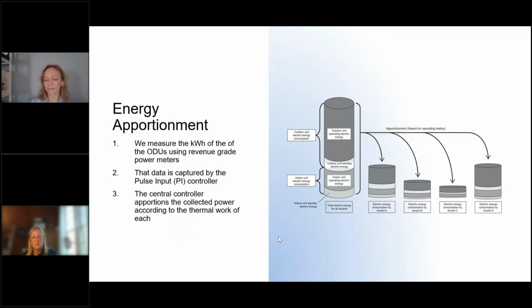As far as energy apportionment, the way it works is we have a revenue grade power meter at the outdoor unit that measures the kilowatts utilized. That data is collected by a pulse input controller, and then a central controller collects all of that data for each indoor unit, where an LEV valve measures the position of the valve and the amount of refrigerant delivered. In this situation, one meter at the outdoor unit can serve up to 200 indoor units.